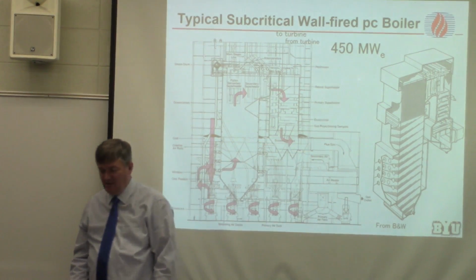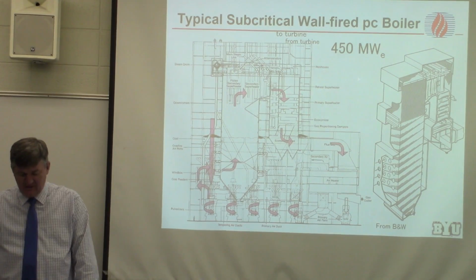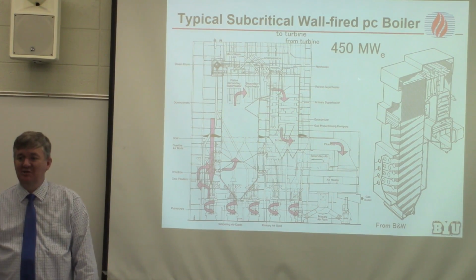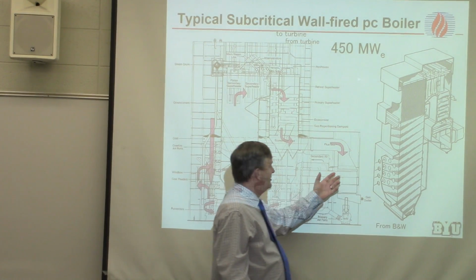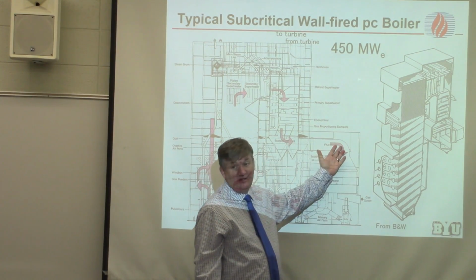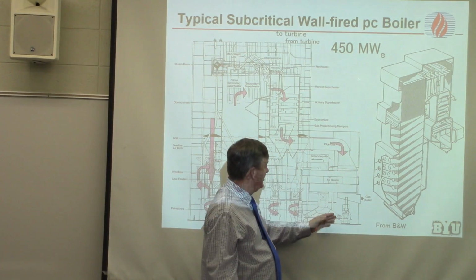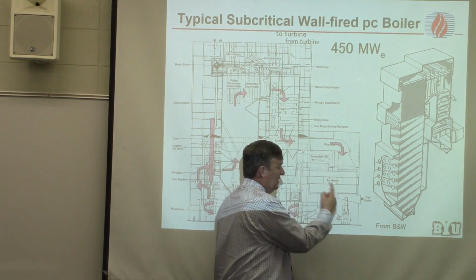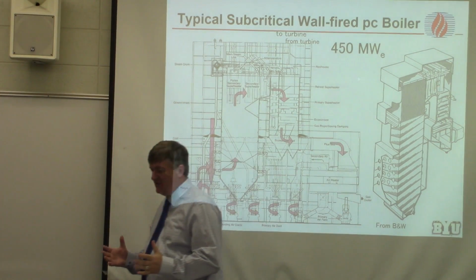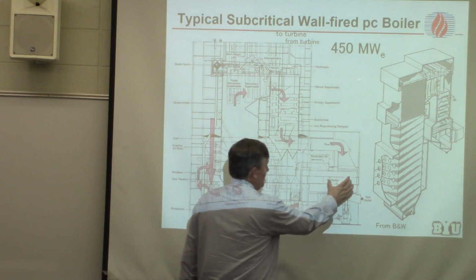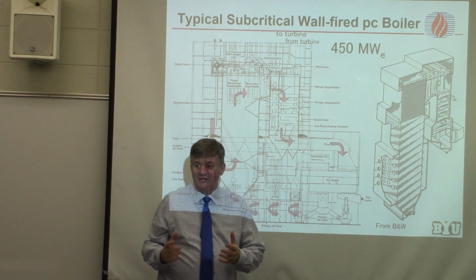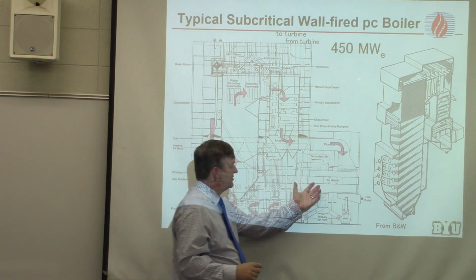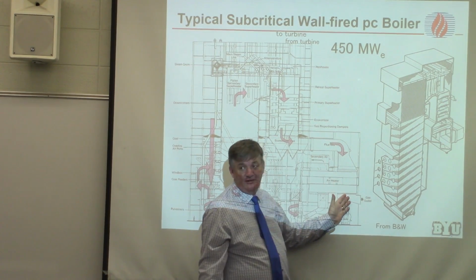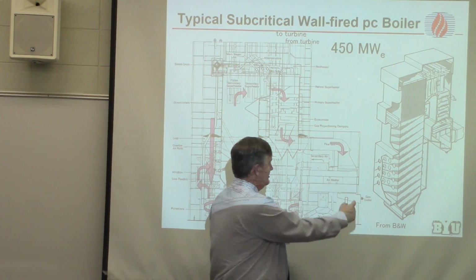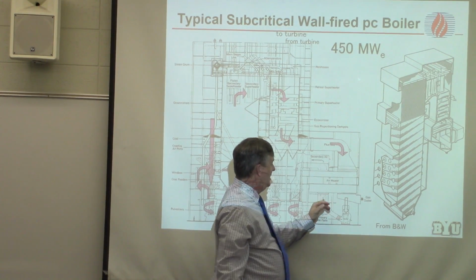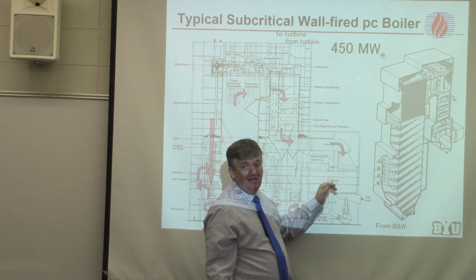And now they're coming out, and you go through a kind of heat exchanger that's pretty amazing. I don't think you ever talked about it in the heat exchanger class. Now you have heat still in this flue gas, and you want to get it into the air that's coming in. So the air is coming through here, and you have this big air heater. The way this air heater works is it has cages full of metal and sometimes rocks, and it just rotates these slowly on a big disc. They rotate in here, and this hot gas goes through these metal and rocks, and then it rotates from there into this, and air is coming this way, and the cold air goes through those hot rocks and metal, and that's the way they do this.